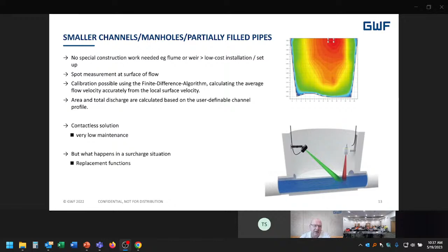And the systems these days can actually switch using a replacement function. So if there's a problem with the velocity measure, we can turn the system into a flow measure using, say, a Manning equation on just the level until such a point that the velocity sensor can be cleaned. So these things have been designed in to allow for continual measurement, even if there are challenges. And if there is an issue, we'll talk in a minute about the capabilities of these transmitters to tell you there's a problem, so you can manage any cleaning or maintenance as required.